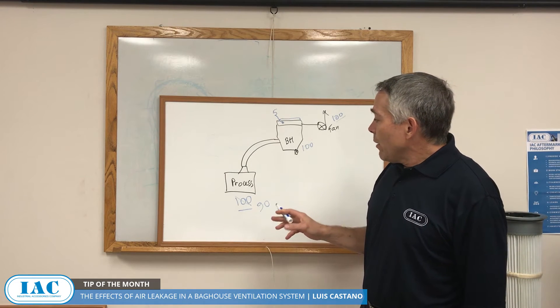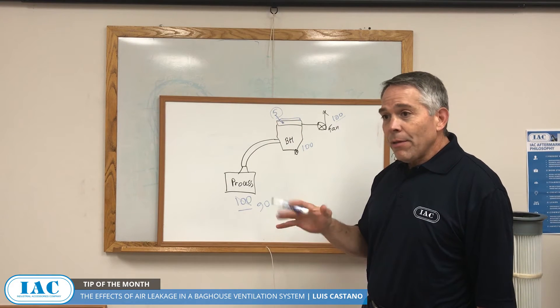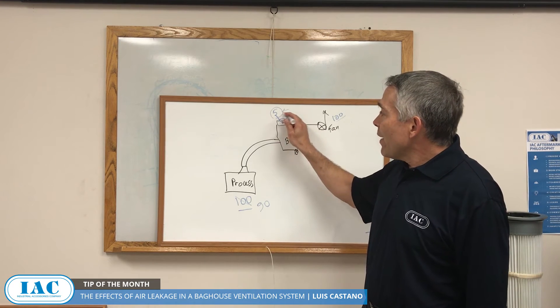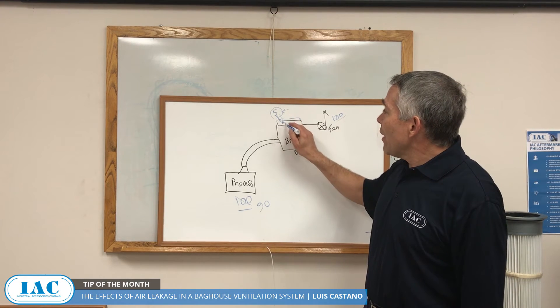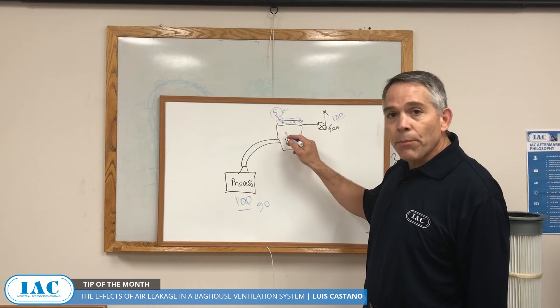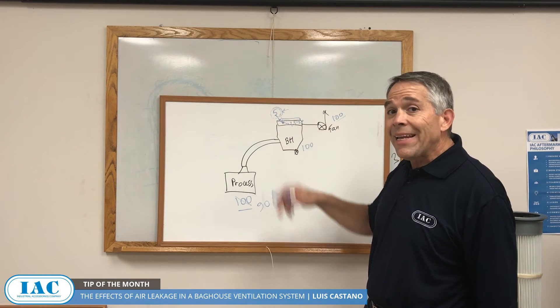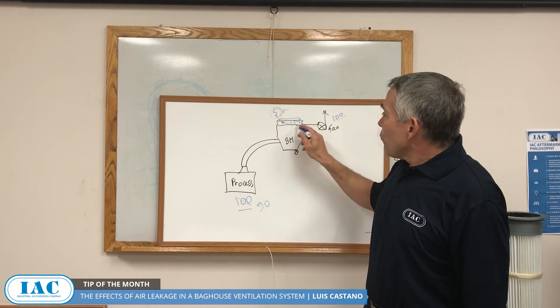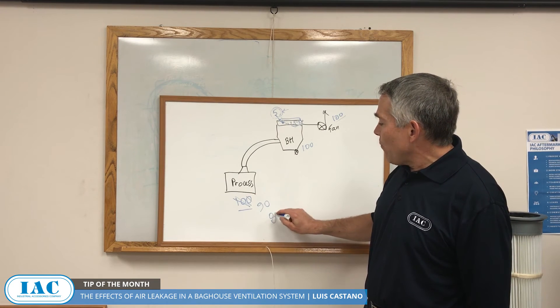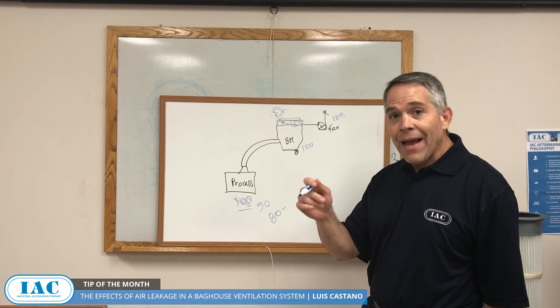If you don't think that small hissing sound is a problem, consider this: if this is a high-temperature system, that 5% at ambient temperature becomes 15% or 20% when dealing with hot temperatures. Because that 5% at 70 degrees, once it goes into your system, it heats up — it grows in volume. So being 15% or 20% means your process is going to get only 80% or 85%, and that's where your system can really suffer in production.